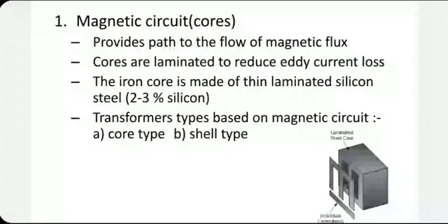Instead of making it a solid assembly, especially in large transformers, we make it out of thin wafers that are cut, as shown in the picture, and then bolted together. That reduces losses, especially eddy current loss.